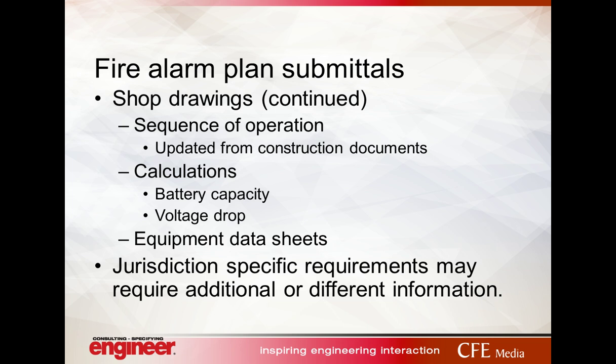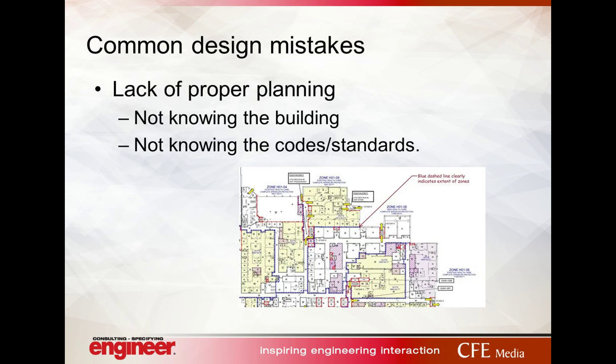Sequence of operation is another requirement on the shop drawings. It's difficult to see how anyone could test a fire alarm system — whether acceptance testing or periodic testing — without a sequence of operations document to reference. Code requirements and NFPA 72 specify what should happen when a device goes into alarm, but the owner may have additional requirements and the design professional may have additional recommendations. All of this needs to be properly documented first in the design documents and then updated in the shop drawings.